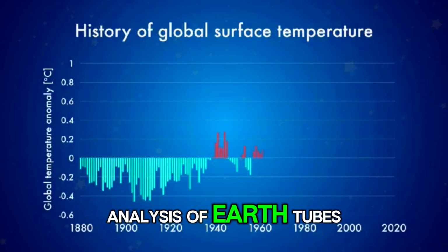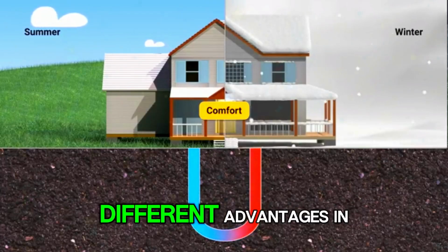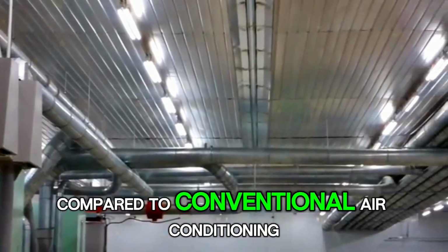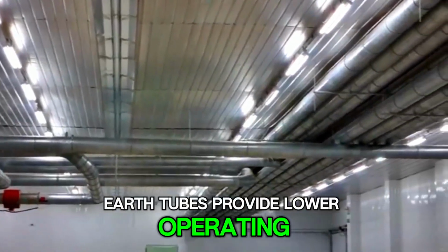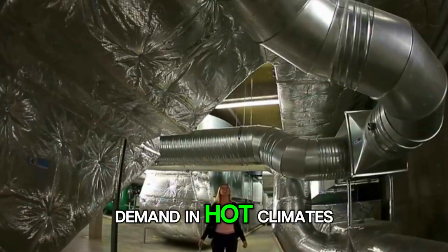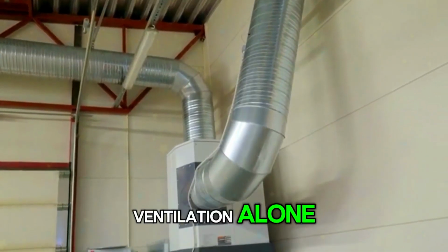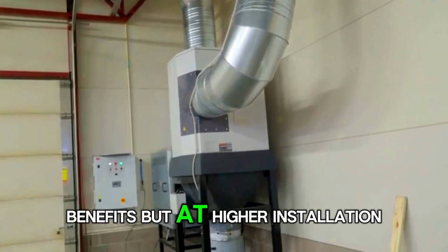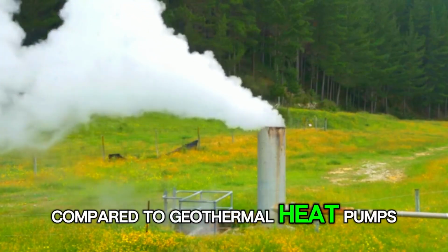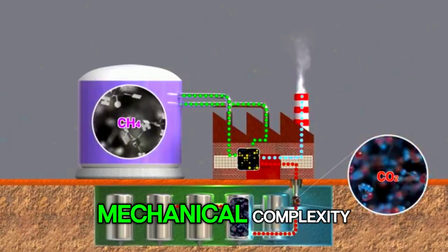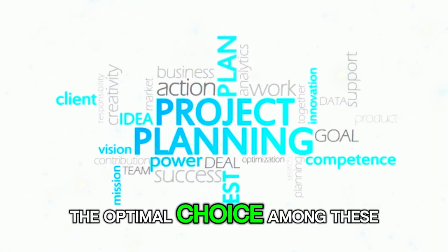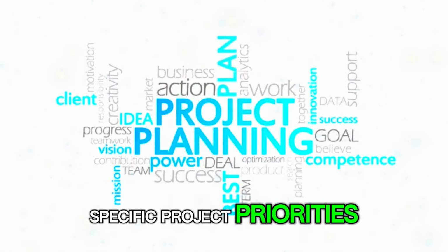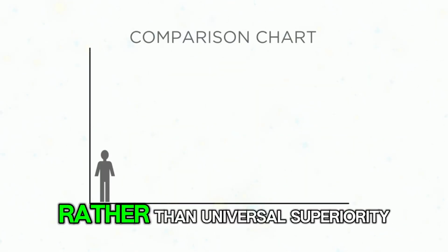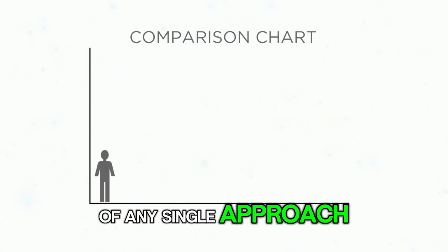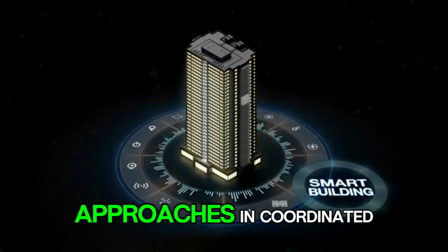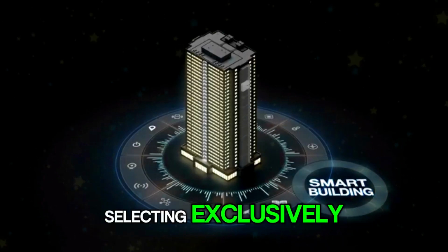The comparative analysis of earth tubes against alternative air conditioning approaches shows different advantages in different contexts. Compared to conventional air conditioning, earth tubes provide lower operating costs but cannot meet all cooling demand in hot climates. Compared to heat recovery ventilation alone, earth tubes add preconditioning benefits but at higher installation costs. Compared to geothermal heat pumps, earth tubes provide passive operation without the mechanical complexity that heat pumps require. The optimal choice among these alternatives depends on specific project priorities, site conditions, and budget considerations rather than universal superiority of any single approach. Many high-performance buildings actually use multiple approaches in coordinated systems rather than selecting exclusively among them.